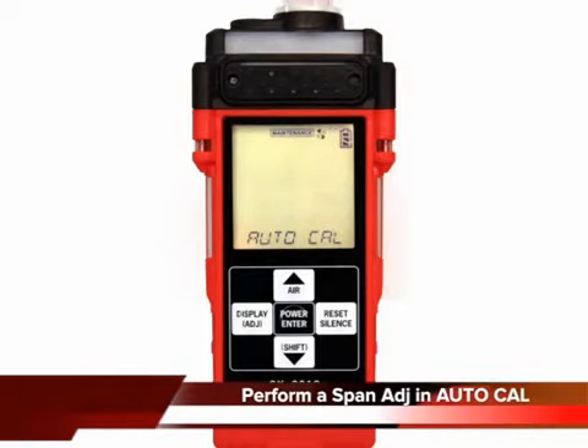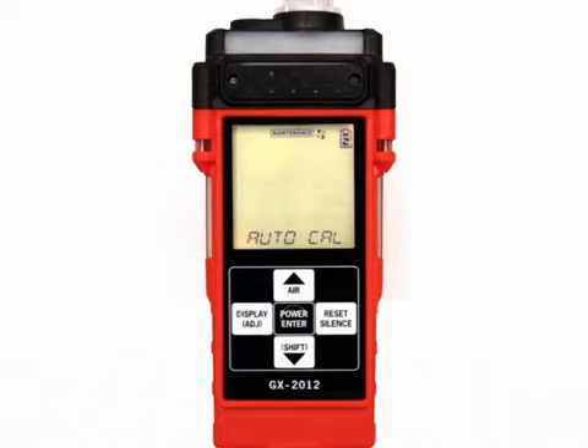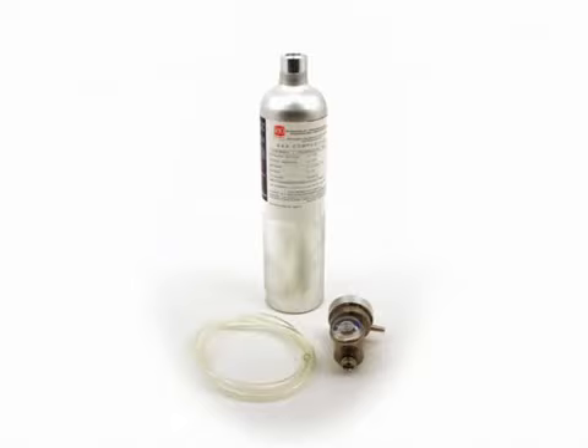The AutoCal menu allows you to perform a span adjustment simultaneously on all channels. Before entering the AutoCal menu, perform a fresh air adjustment. Performing a span adjustment requires the use of a calibration kit. The following procedure describes a span adjustment of all 5 channels using a calibration kit that includes a 4-gas calibration cylinder, a percent volume methane cylinder, a demand flow regulator, and non-absorbent sample tubing.